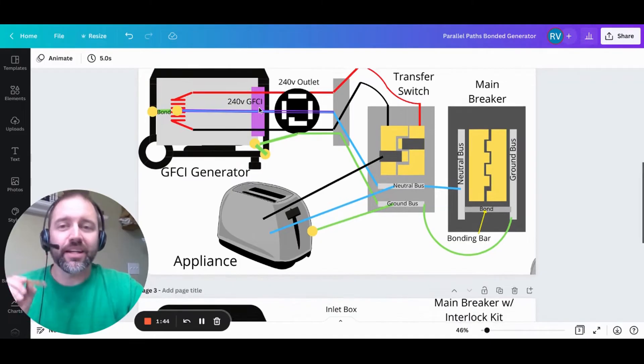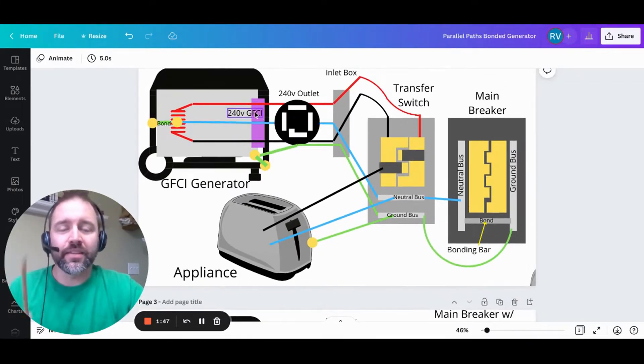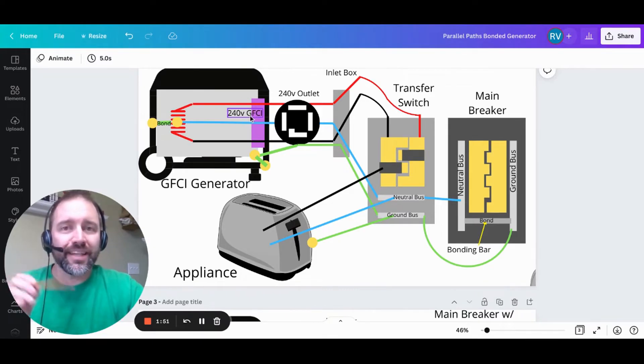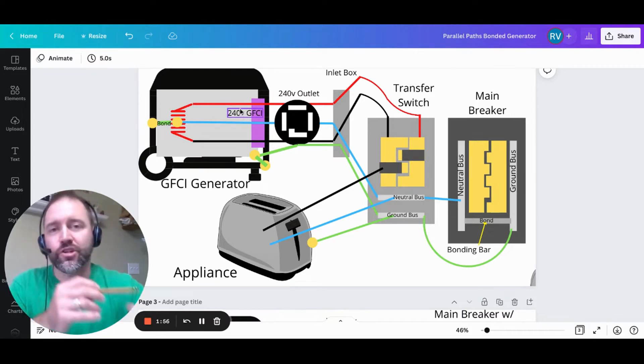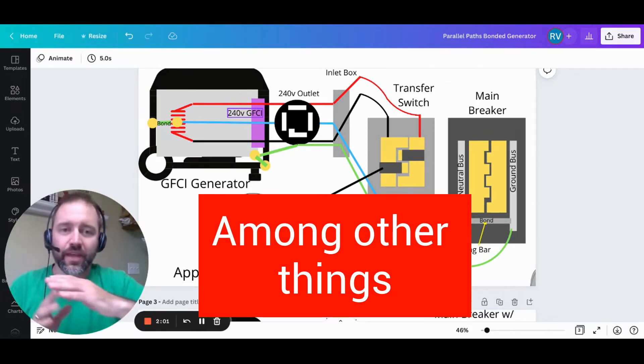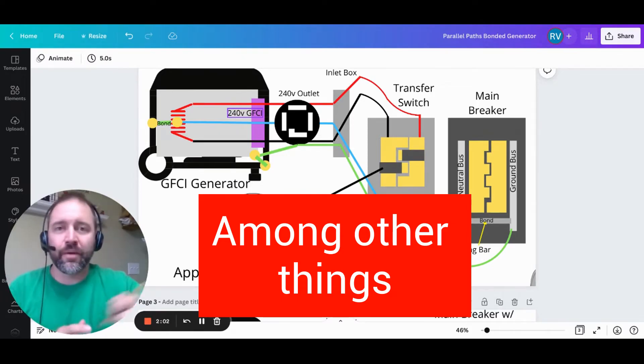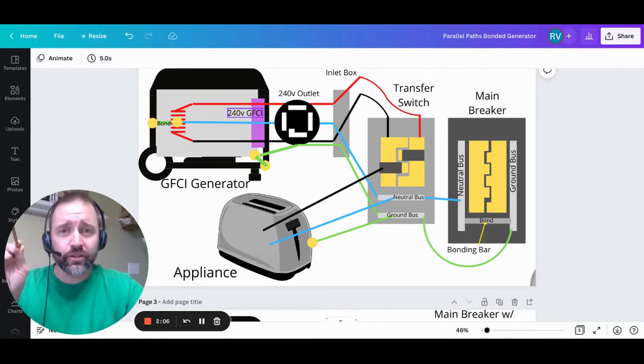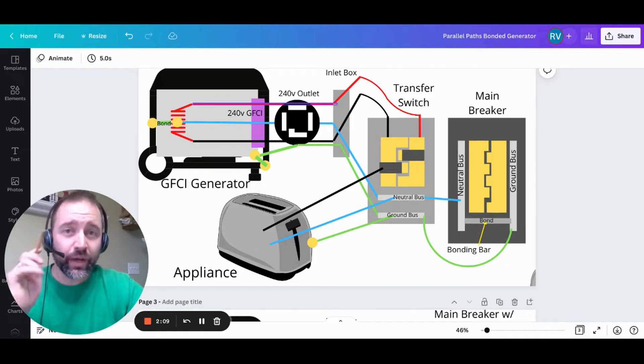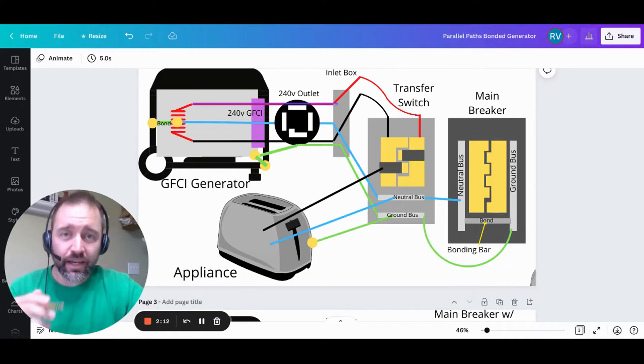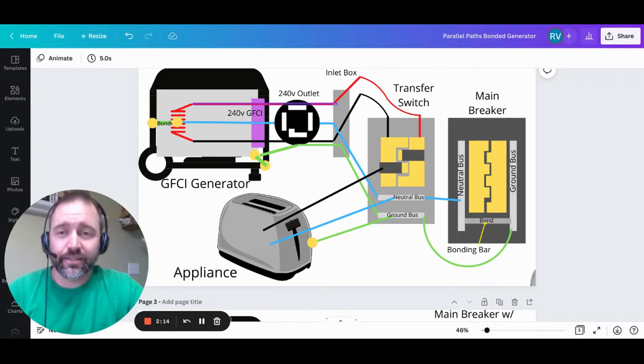Keeping that in mind, a GFCI breaker or outlet, in this case we're going to be looking at a breaker, a ground fault circuit interrupt breaker, measures the outflow of the current and it measures the return current coming back. If there's a discrepancy between the two, it will trip, and then it'll cut power from everything downstream of it. So again, electricity wants to go in a circle or a circuit, and a GFCI breaker will measure what's going out, what's coming back, and if there's a difference, it trips.